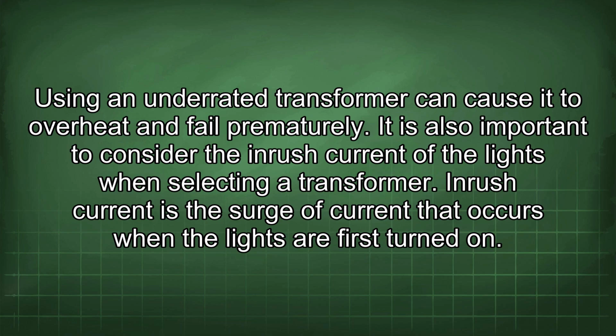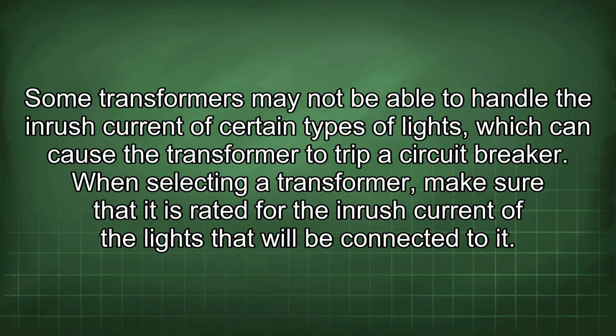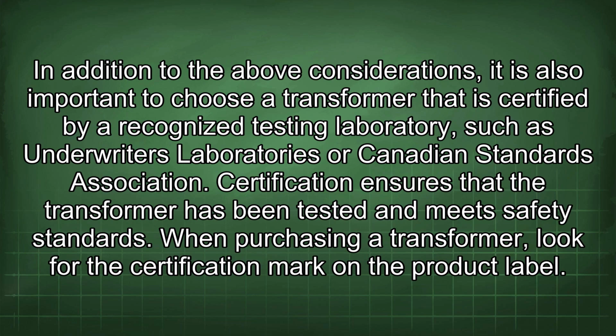It is also important to consider the inrush current of the lights when selecting a transformer. Inrush current is the surge of current that occurs when the lights are first turned on. Some transformers may not be able to handle the inrush current of certain types of lights, which can cause the transformer to trip a circuit breaker. When selecting a transformer, make sure that it is rated for the inrush current of the lights that will be connected to it.